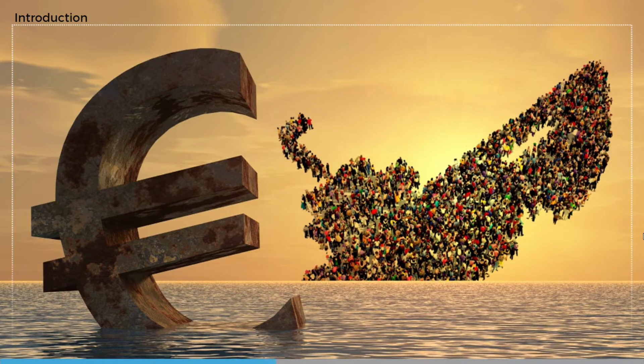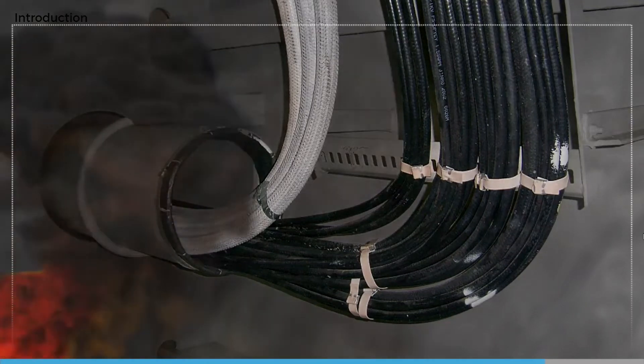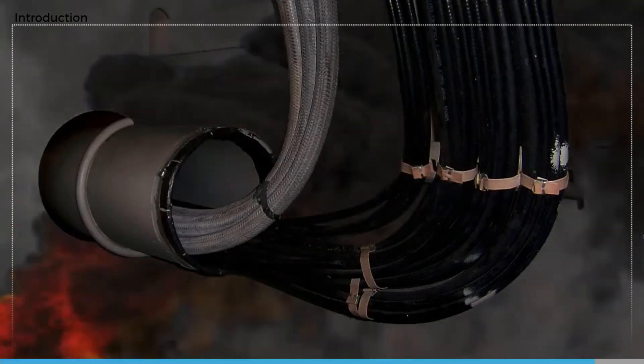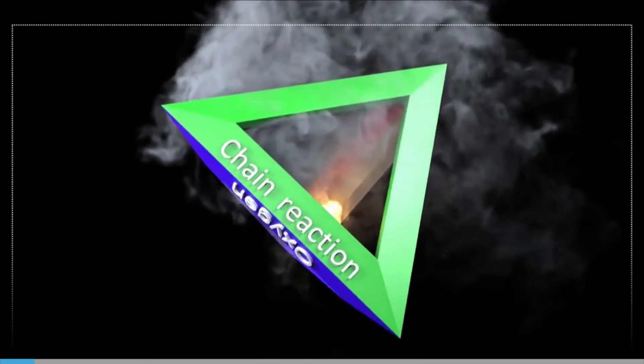Prompt action for an engine room fire is especially important because the most serious fires are those caused by oil, usually under pressure, escaping from running machinery. The resultant fires produce high temperatures and smoke which, in compact machinery spaces, quickly reduce visibility and access to fight the fire. The heat buildup can also quickly lead to secondary damage to other machinery, particularly electrical cables and control and instrumentation systems.